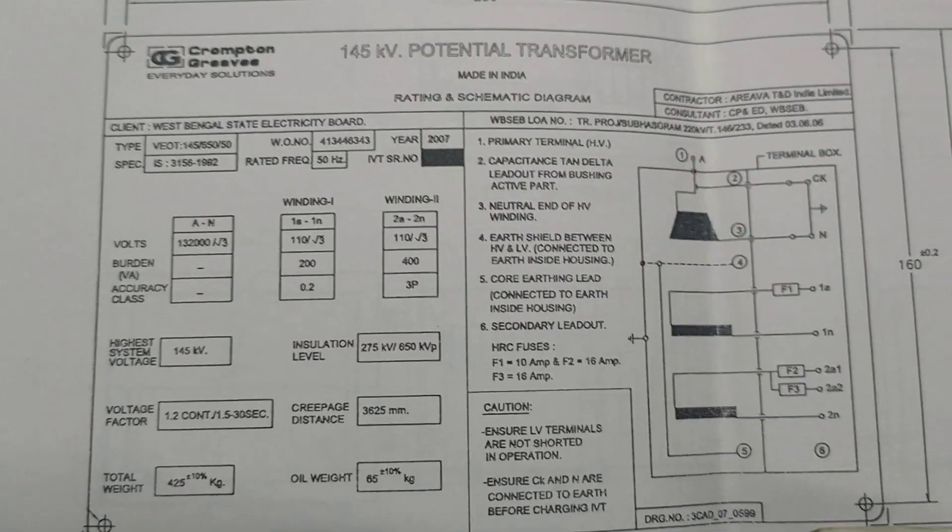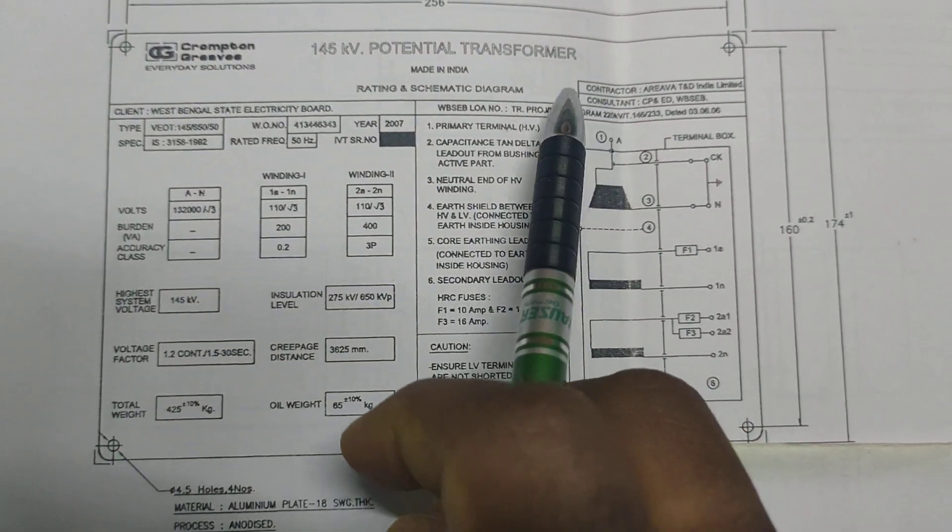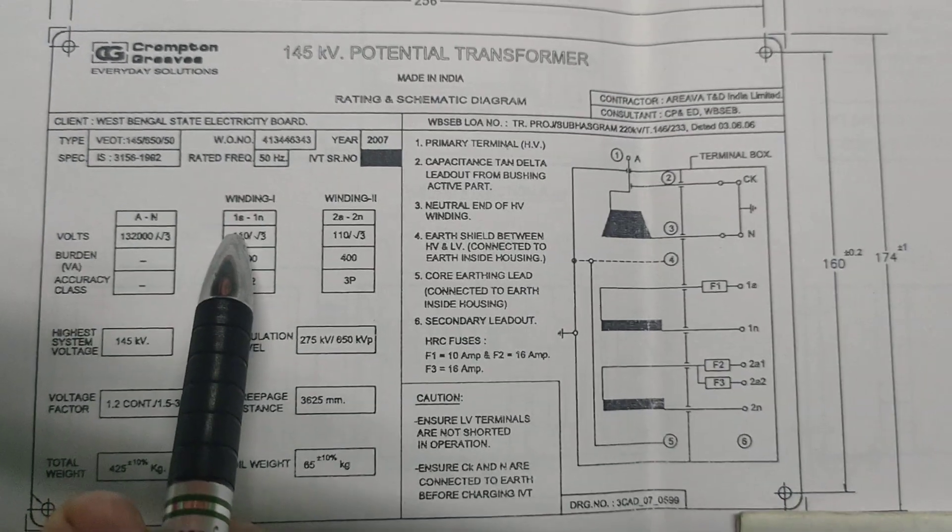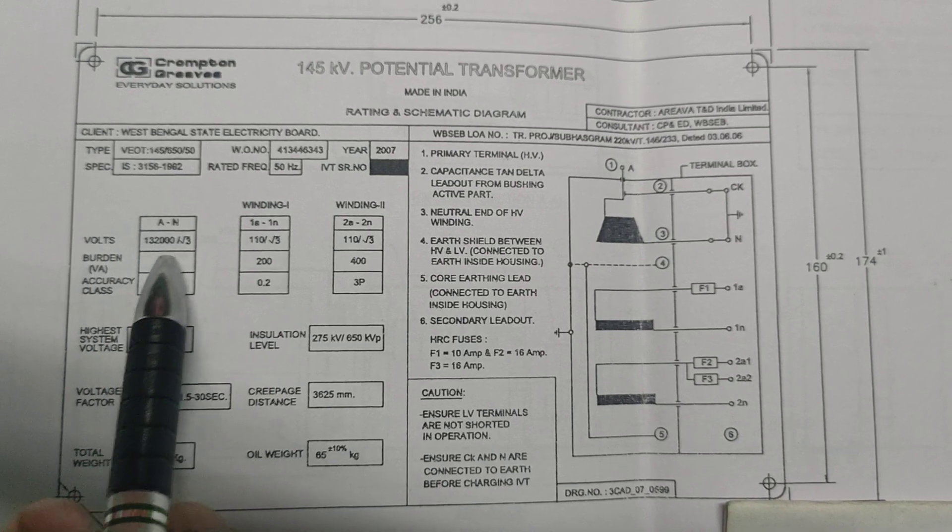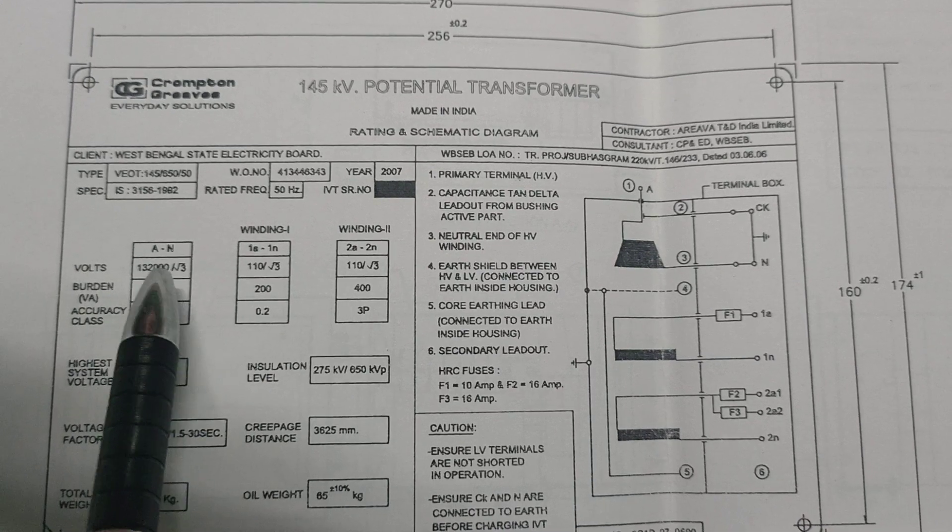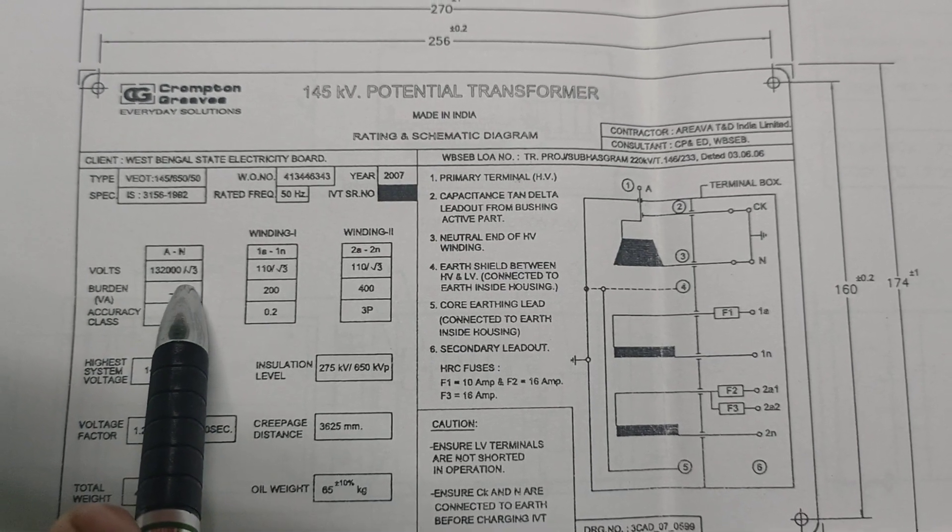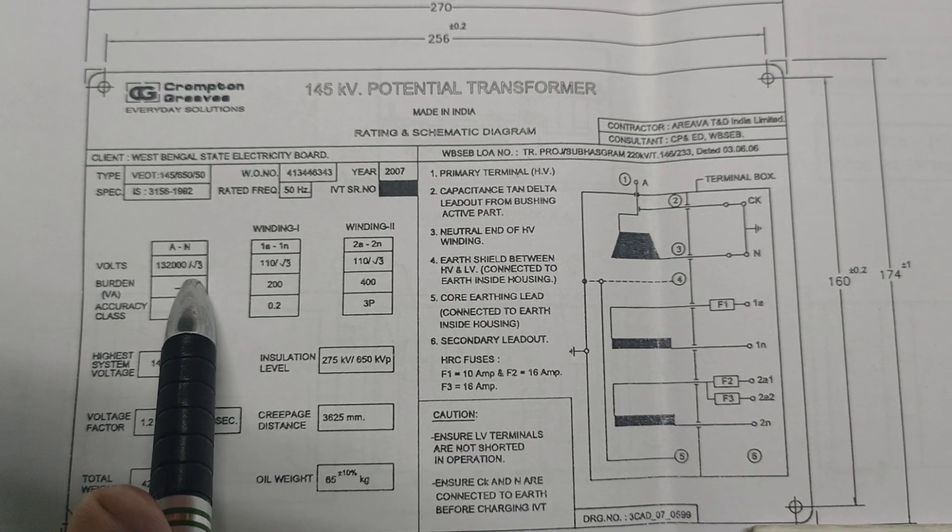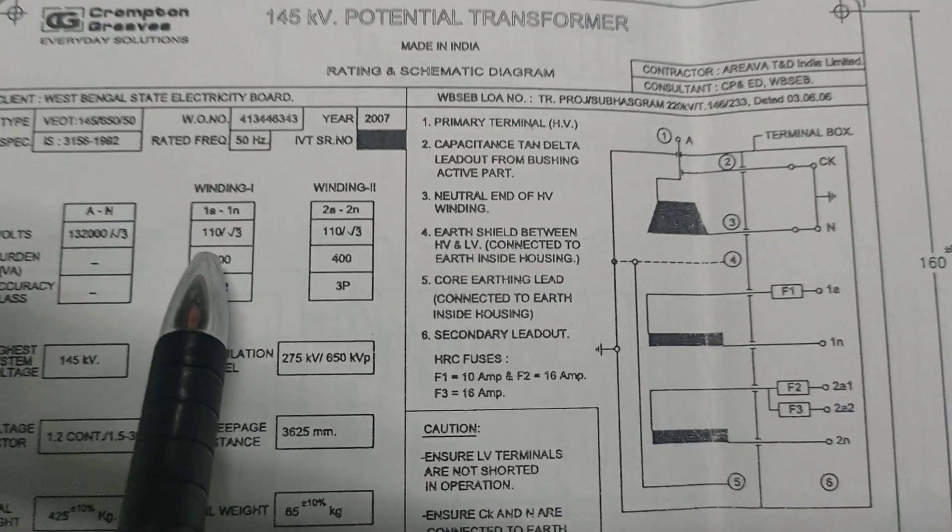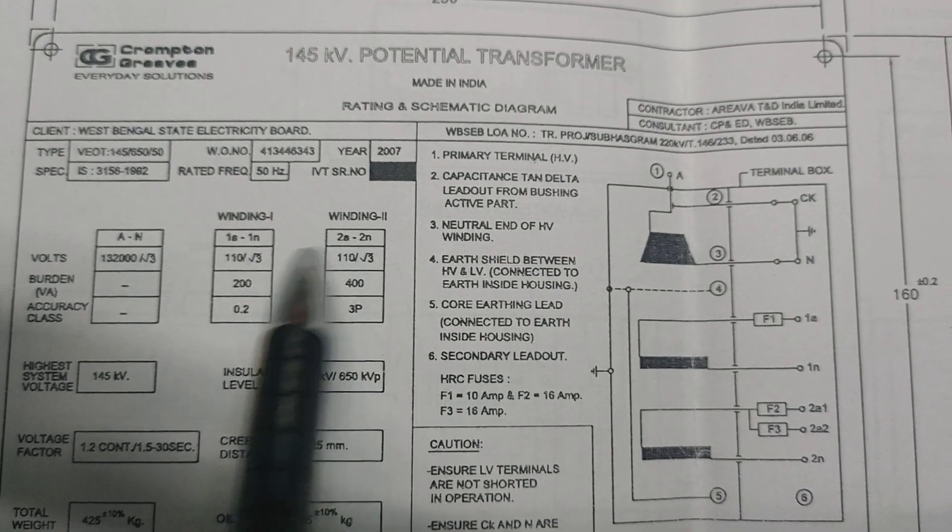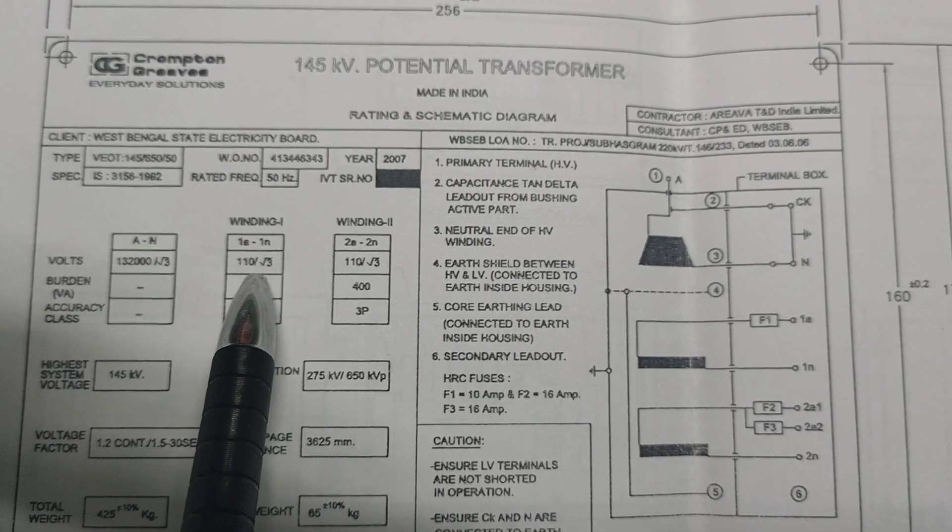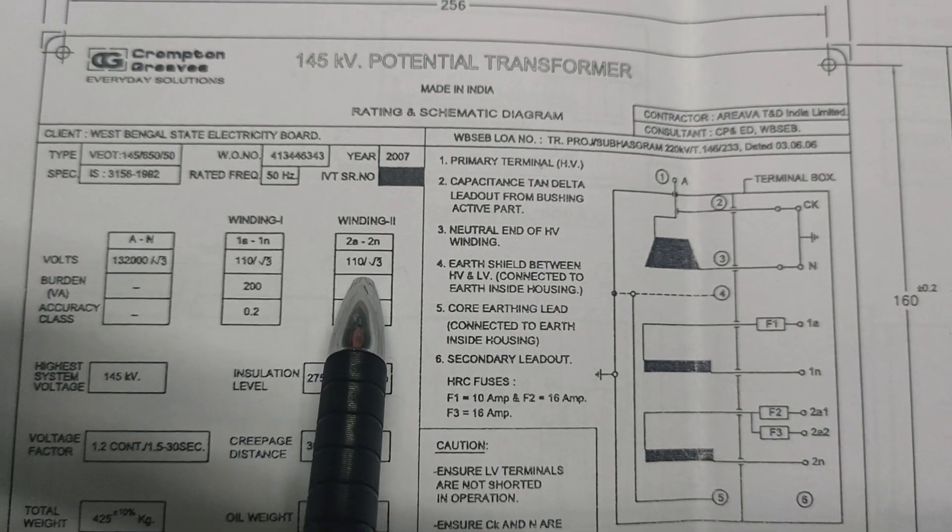Now we discuss the nameplate of the 145 kV potential transformers. This is the core. A or N is the primary core. 132,000 divided by root 3 is the phase voltage, that may be 76 kV nearest. This is winding 1 and winding 2. Winding 1 is denoted by 1A1N and winding 2 is denoted by 2A2N. Winding 1 voltage is 110 divided by root 3, and winding 2 will be obviously the same, 110 by root 3.